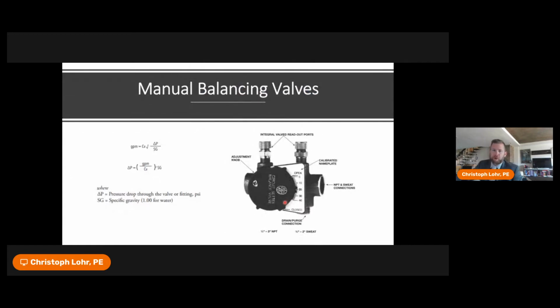In terms of valves, this is where we get a key note: most of the industry has utilized manual balancing valves, such as this type, which is probably the most common way, where there are 2 integral readout ports and a control valve on the side. A lot of people think incorrectly that this is talking about GPM. It is talking about CV. As you can tell from the equation here, CV is inversely proportional to the change in pressure through the valve, and it is directly proportional to the flow rate. Specific gravity we can ignore because it's 1 for water. So this is the part of the sort of the challenge.